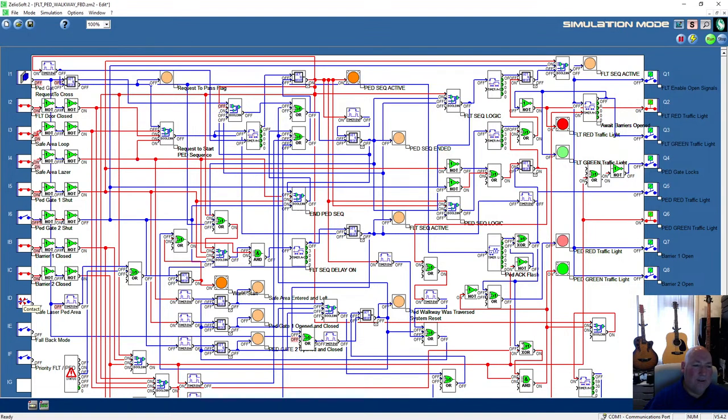It's off a laser scanner with dual outputs. Output 2 is default safety, but output 1, which defaults to an open command or open signal, I'm going to change to safety as well. And so we'll have one area that covers from the barrier corner, underneath the barrier, all the way across the road crossing, all the way up to the shutter door.